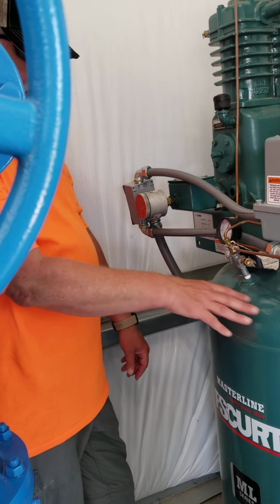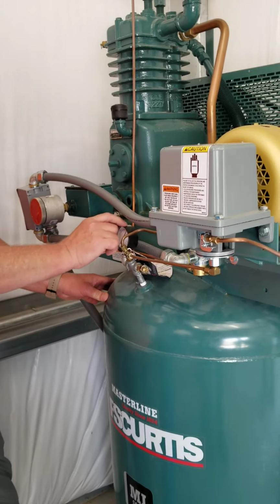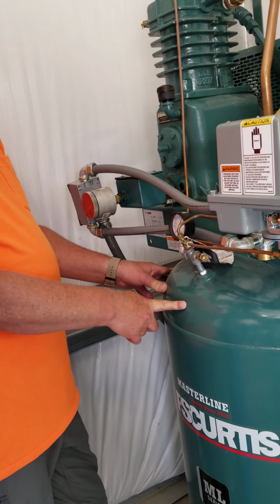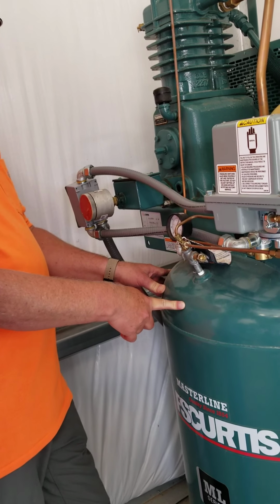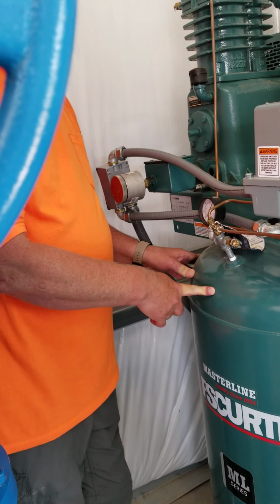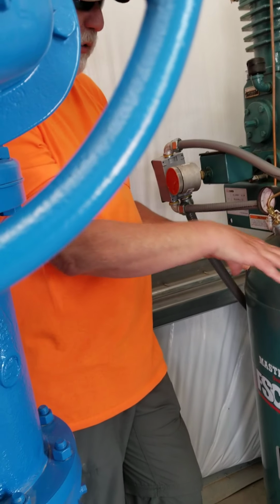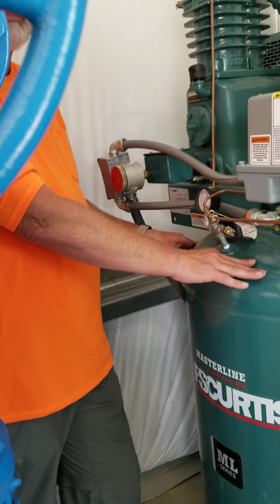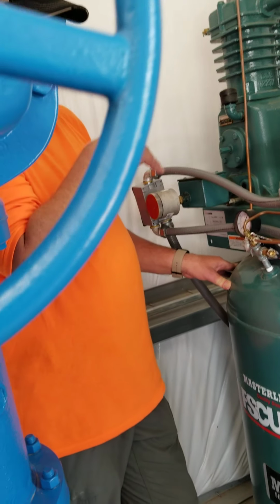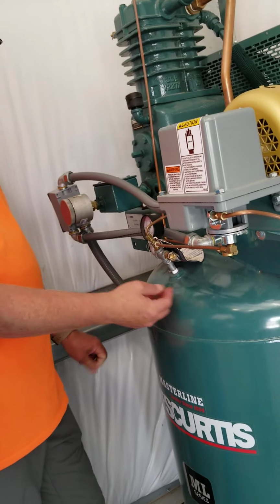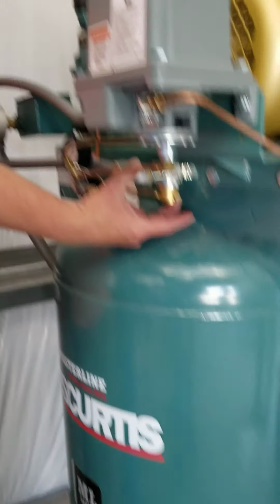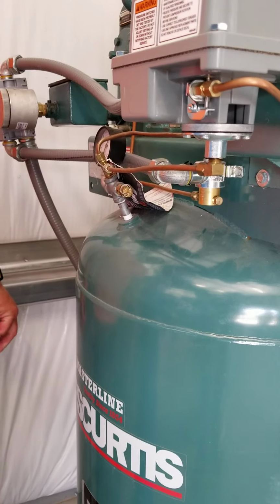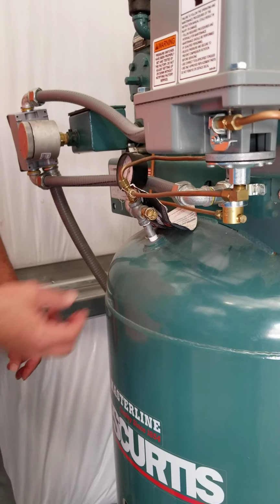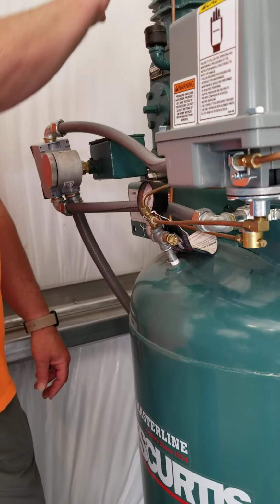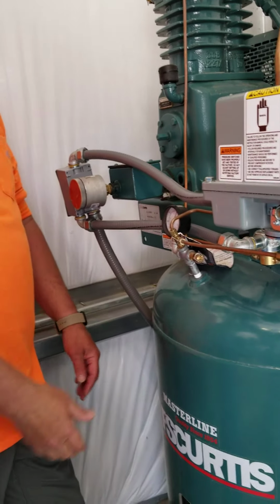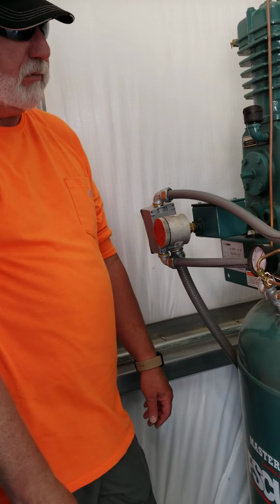You have a receiver tank, a pressure gauge, which is reading the pressure in the receiver tank. These are pretty much self-contained units, so they are going to pressurize their receiver tank and stop at that point until it's called for air. This solenoid valve is an unload solenoid valve. That is normally open, so when the compressor's off, the solenoid is open. It takes pressure off of the heads so that the units start not under a load.